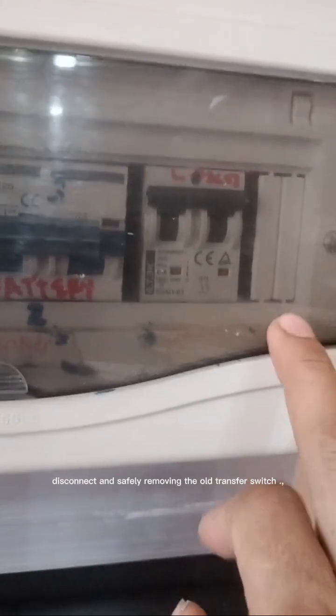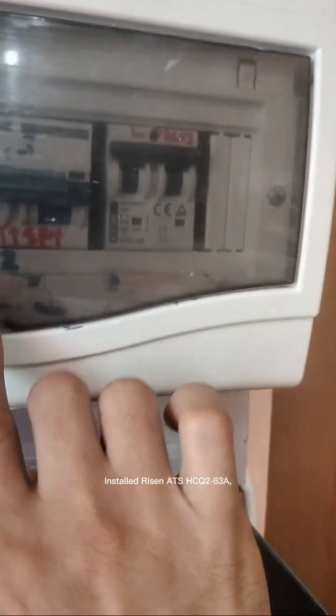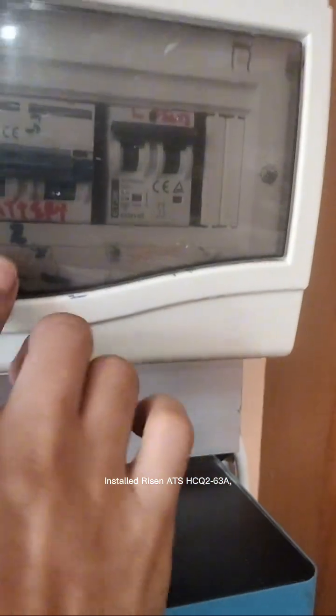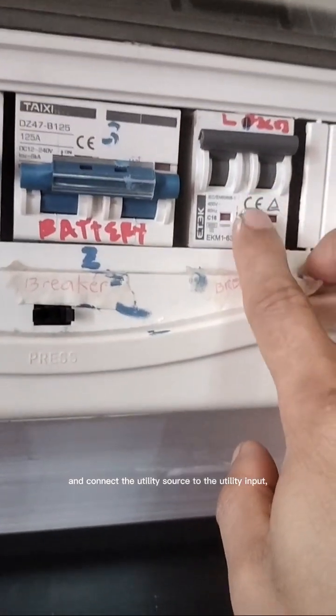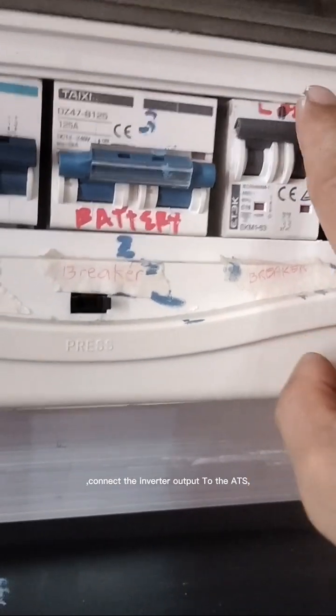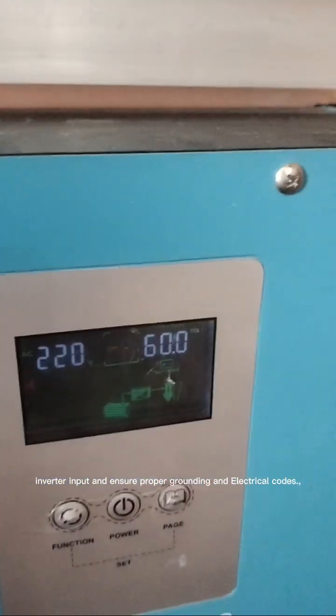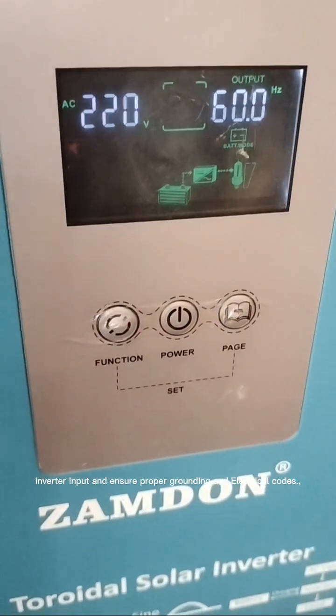Retrofitting steps will be carried out, such as removing the existing RSW6-100, disconnecting and safely removing the old transfer switch. Install the Risen ATS HCQ2-63A and connect the utility source to the utility input, connect the inverter output to the ATS inverter input, and ensure proper grounding and compliance with electrical codes.